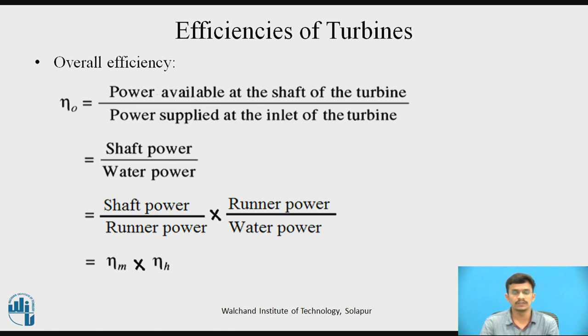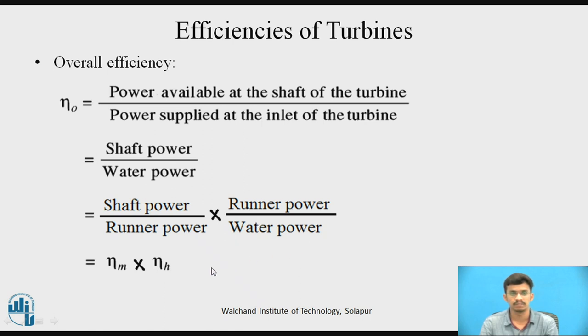The overall efficiency of the turbine is defined as the power available at the shaft of the turbine to the power supplied at the inlet. Shaft power divided by water power gives the overall efficiency. Dividing and multiplying by runner power, this becomes shaft power over runner power, multiplied by runner power over water power. Since shaft power to runner power is mechanical efficiency, and runner power to water power is hydraulic efficiency, overall efficiency equals mechanical efficiency multiplied by hydraulic efficiency.